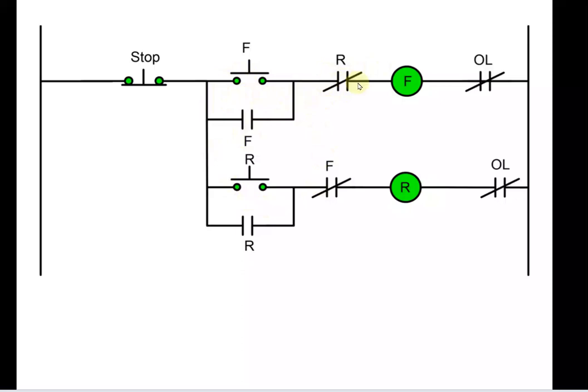The auxiliary interlocking is wired in series with the opposite coil. This method of wiring the coils through the opposite auxiliary normally closed contacts prevents the coils of the starter from being energized at the same time — which could be very dangerous if not wired correctly. This reversing starter contains a mechanical interlocking device to lock out the coils from being energized at the same time. There are different buttons: a stop button, forward push button, and reverse push button. This is shown as a ladder diagram or PLC diagram.